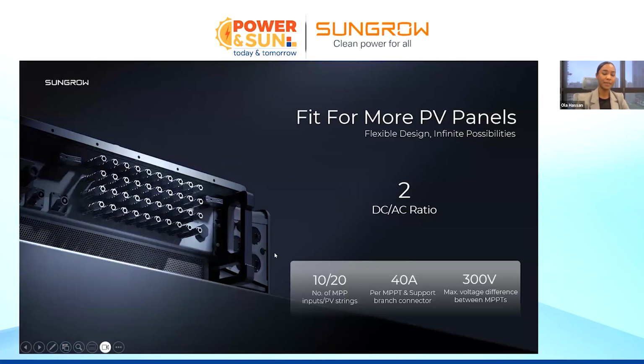So 200% DC-AC ratio, which is great. That means we have the same inverter rated capacity to feed the load and also the same inverter rated capacity to charge the battery as well. This inverter will have up to 10 MPPTs and each MPPT has 2 inputs, giving us 20 inputs. So big flexibility when we are designing our PV strings, 40 amps per MPPT. And in case we have different lengths of strings, the inverter can withstand up to 300 volts of MPPT voltage difference.